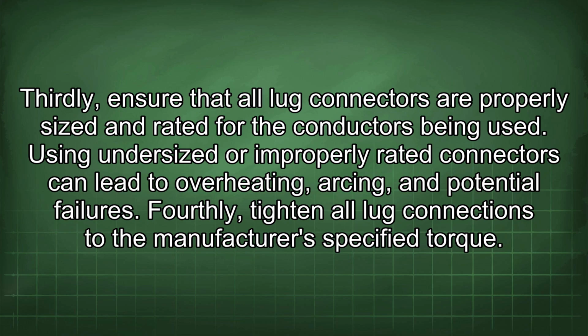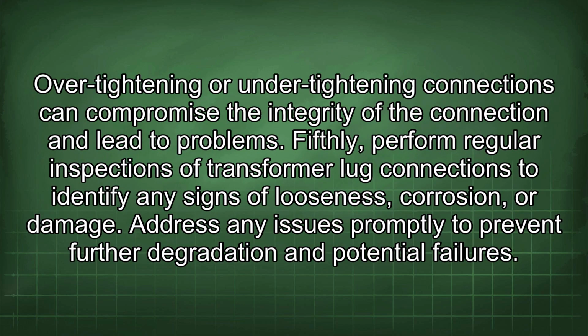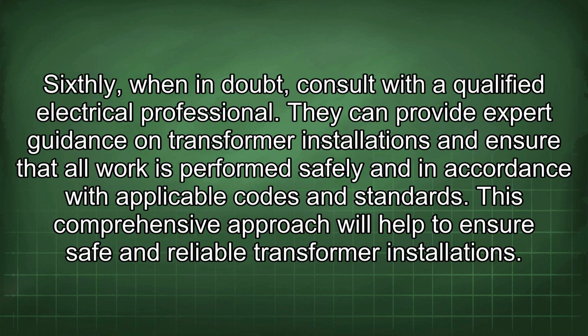Fourthly, tighten all lug connections to the manufacturer's specified torque. Over-tightening or under-tightening connections can compromise the integrity of the connection and lead to problems. Fifthly, perform regular inspections of transformer lug connections to identify any signs of looseness, corrosion, or damage. Address any issues promptly to prevent further degradation and potential failures. Sixthly, when in doubt, consult with a qualified electrical professional. They can provide expert guidance on transformer installations and ensure that all work is performed safely and in accordance with applicable codes and standards. This comprehensive approach will help to ensure safe and reliable transformer installations.